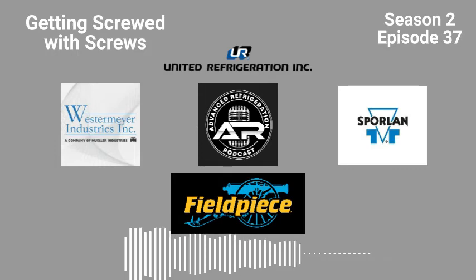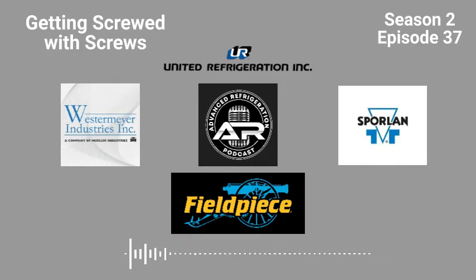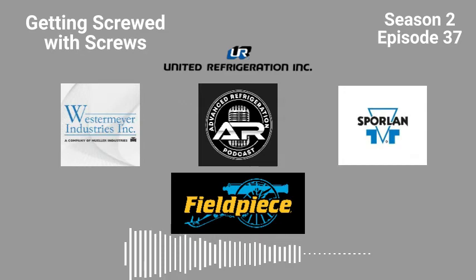And those motors are extremely hard to get. They aren't just sitting on a shelf, and they're like $600 for a 2-speed. How much is this motor? $900? And you got to go to the OEM to get it? It's insane. You're talking an ECM motor you can get for like $150 that slaps in there and saves the same amount of energy.